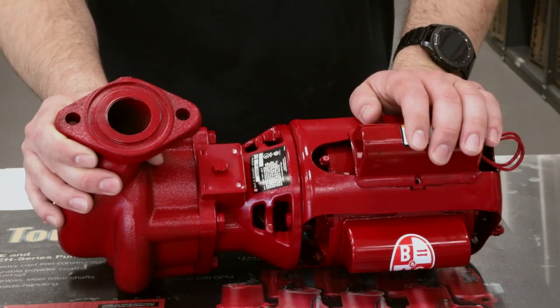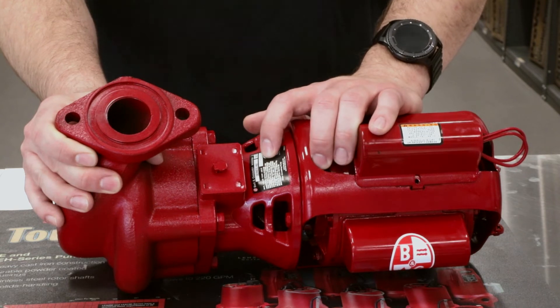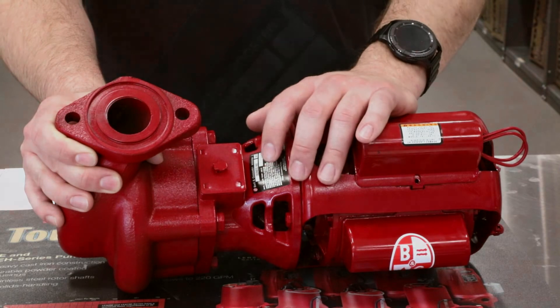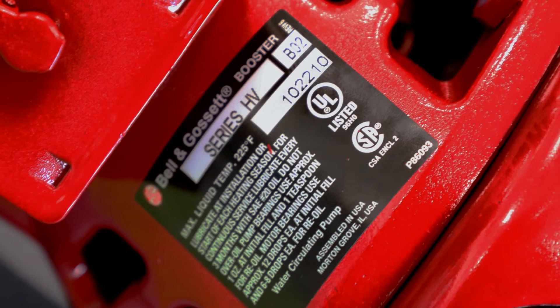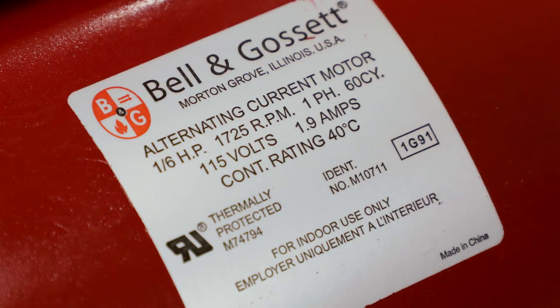On this Bell & Gossett inline circulator pump, the tag is right here. This is actually going to be on the bearing assembly and not the volute. The model number is 102-210 as part of the series HV line, and on the motor tag it states that it's 1/6 horsepower, 1725 RPM, single phase, 115 volt pump.